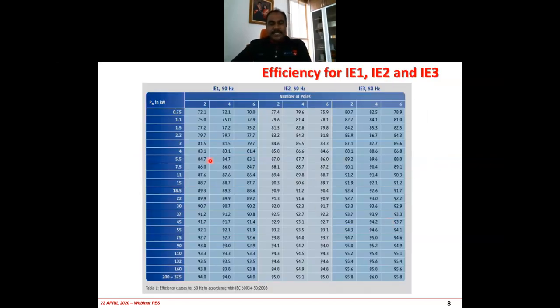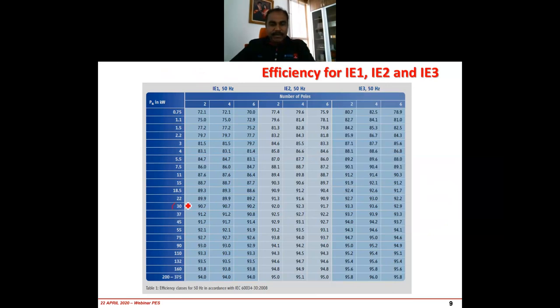Now, in tabular form, this is actually tabulated, which you can just Google and get from IEC 60034. Again, the power rating and various poles, and we have IE1, IE2, IE3. So as you can see from here, for example, let's say we focus on 30 kilowatt for all the IE1, IE2, IE3. You notice that IE1 is 90.7, IE2 is 92.3, and IE3 is 93.6. So obviously you can see there is about 2% difference approximately, an improvement in efficiency from IE1 to IE2 to IE3.